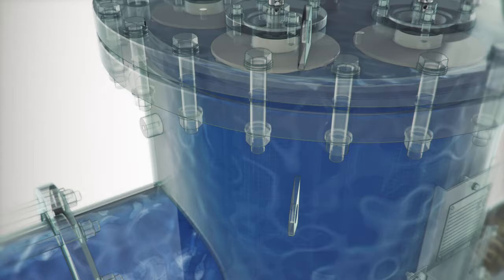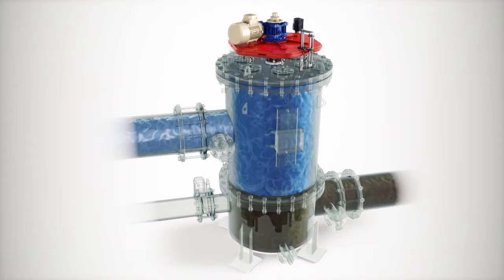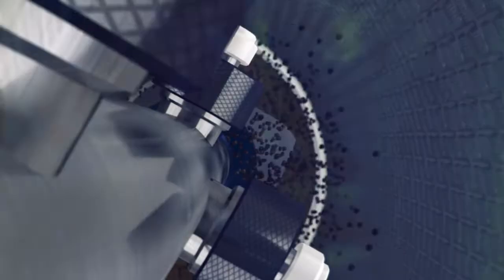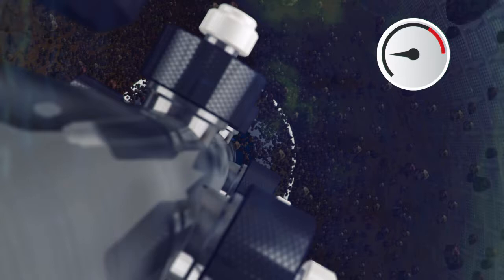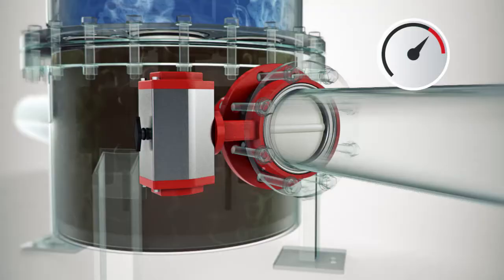The PLC constantly monitors differential pressure development across the filter by means of a DP transmitter. In the process, suspended solid particles are trapped and accumulate on each screen's inner surface. Once the differential pressure reaches a preset level, the system activates its self-cleaning cycle by opening the flushing valve and starting the motor.